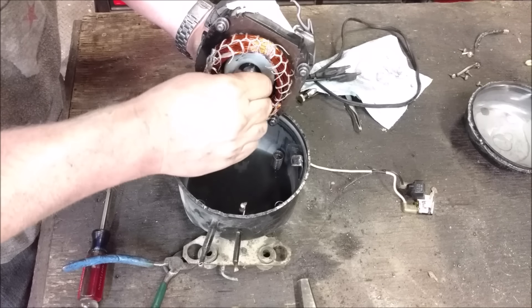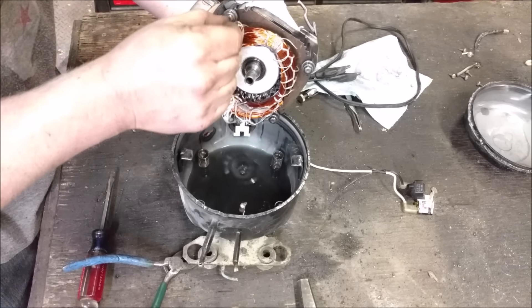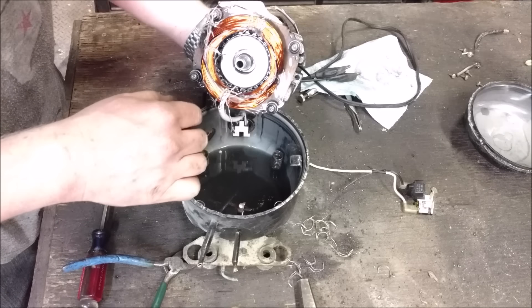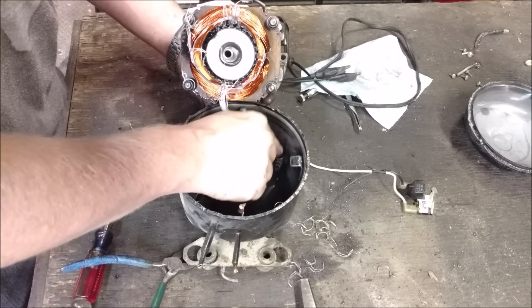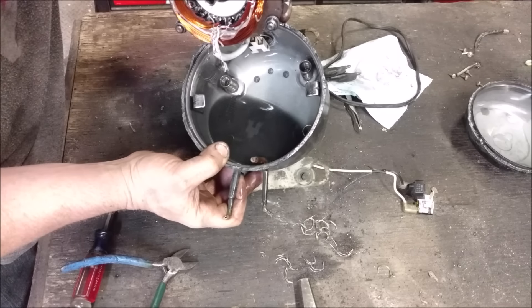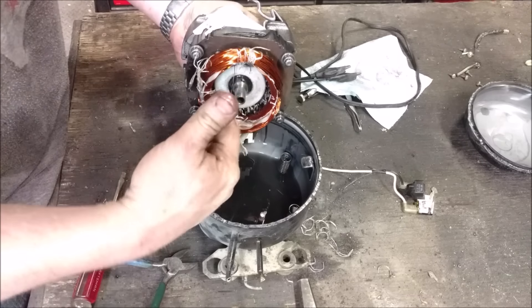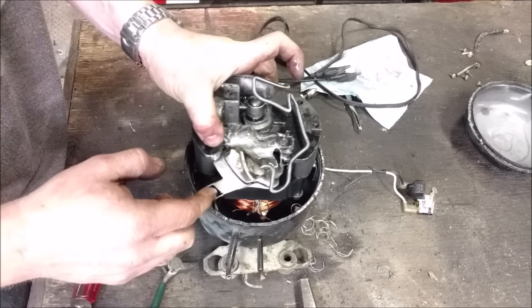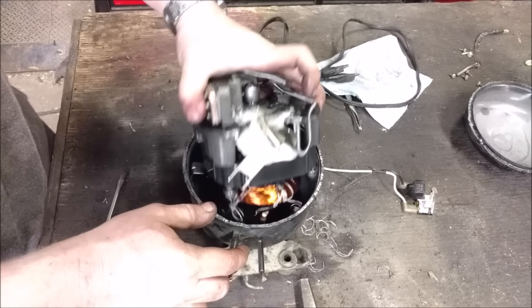And you can see the electric motor — it spins actually pretty nice. A lot of these have overheated to the point that it's ripped all the lacing that keeps all the wires together. And then we've got some nice springs — they're just sitting in the same oil. There's really no debris — a little bit down there — but generally oil gets pulled up through here and flung around and pushed up through this center hole right here, splashing over everything and lubricating the entire system.